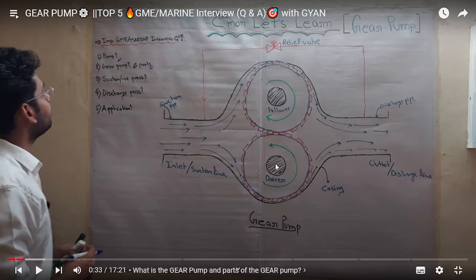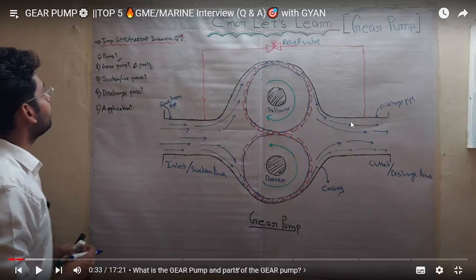It's a 2D figure so the motor shaft is not shown. When the driver gear rotates anti-clockwise, the follower gear rotates clockwise. A gear pump is a type of positive displacement pump which transfers fluid from one place to another by means of mechanical meshing of gears. When the teeth rotate they mesh with each other, and because of this mechanical force the fluid gets transferred. There must be a suction pressure — a negative pressure — created at the inlet, and discharge pressure created at the outlet.